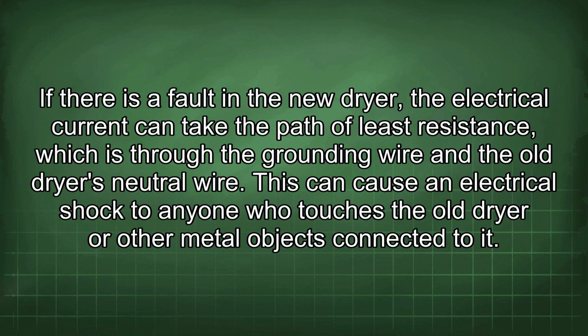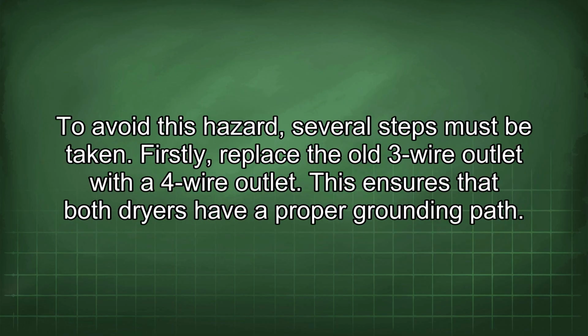If there is a fault in the new dryer, the electrical current can take the path of least resistance, which is through the grounding wire and the old dryer's neutral wire. This can cause an electrical shock to anyone who touches the old dryer or other metal objects connected to it. To avoid this hazard, several steps must be taken.